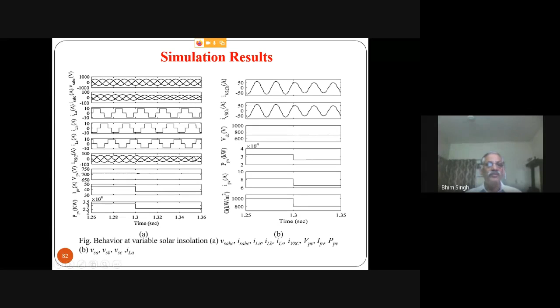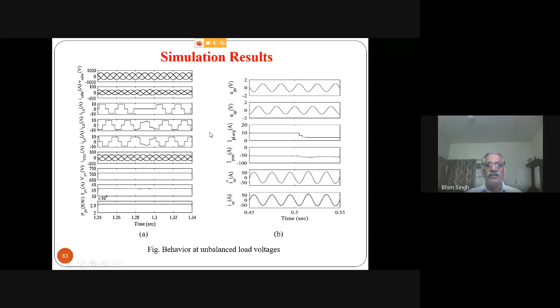And here are the control signals - the template, quadrature and phase template estimated from the distorted voltage, then the net component of the load active current for all three phases, then the solar feed-forward and the PI controller outputs, all multiplied together to get the net template, giving the reference current. This is the actual current flowing into the grid, which has to follow the reference because of the current controller.